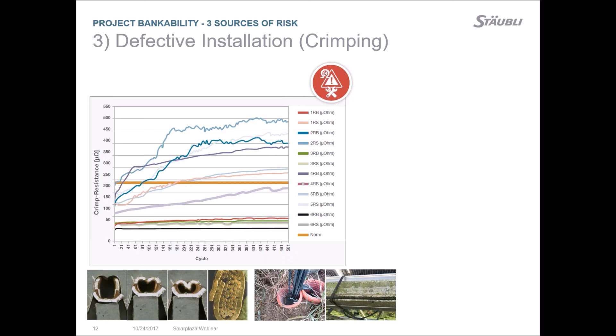Crimping with a non-certified tool, or just with pliers, is really critical—it may not fulfill the norm criteria, and you'll have no stable contact resistance and no gas tightness. This figure again shows contact resistance curves for different crimping connections, with increasing contact resistance, which can lead to the consequences already mentioned.